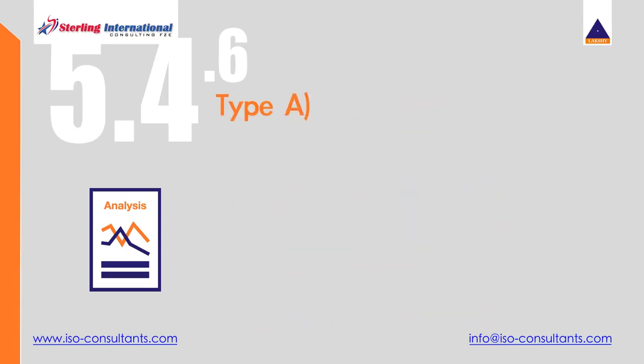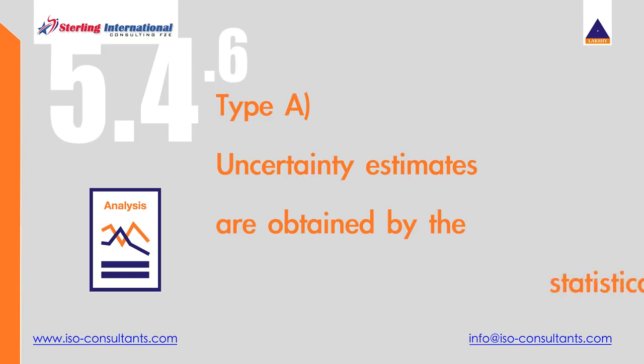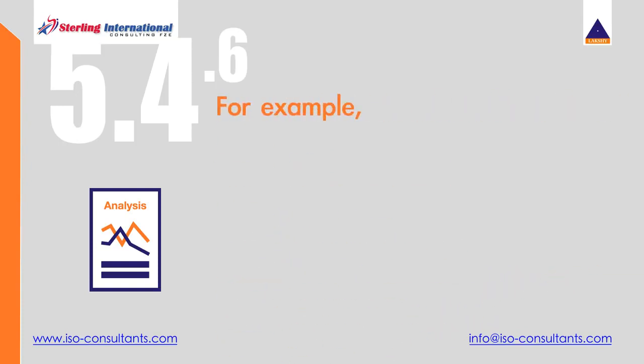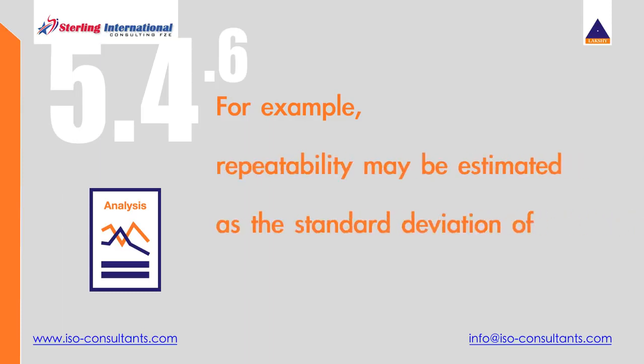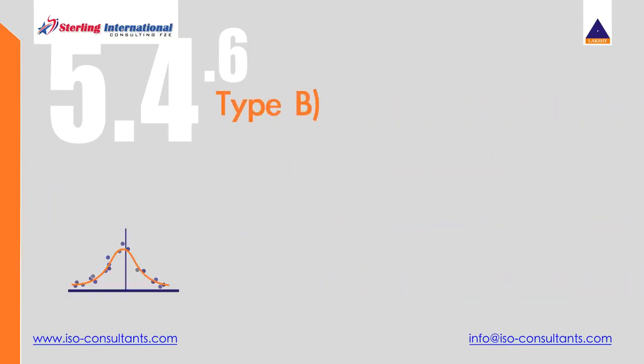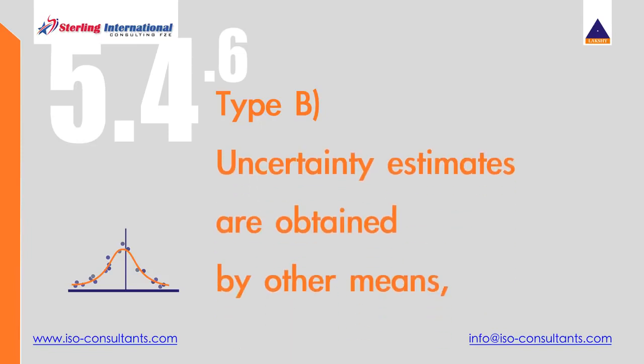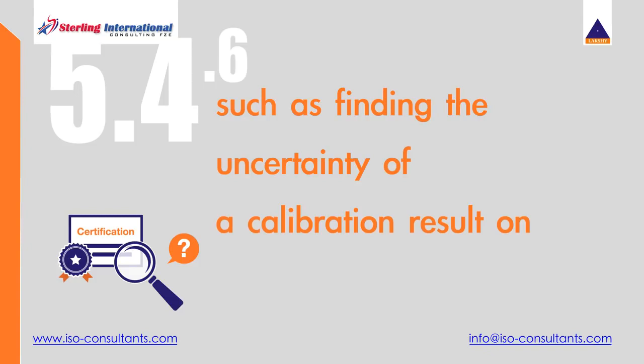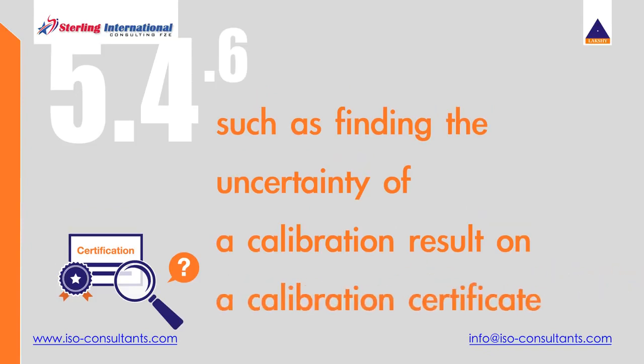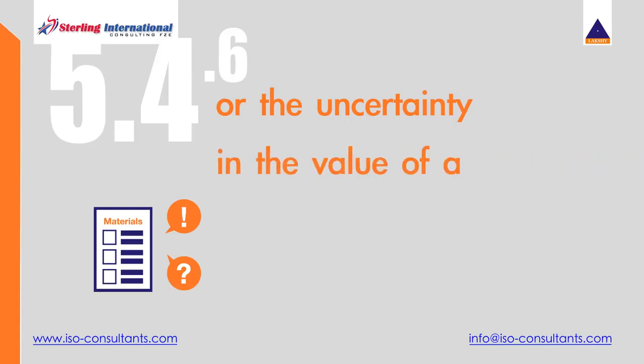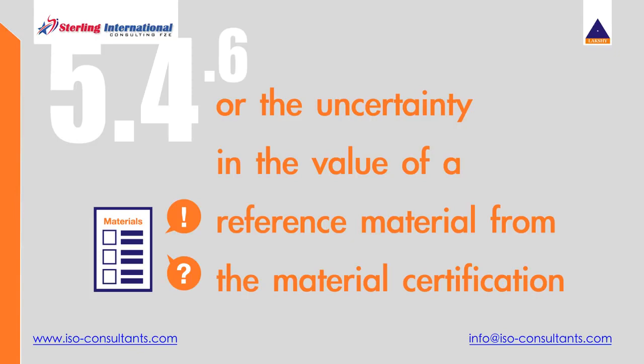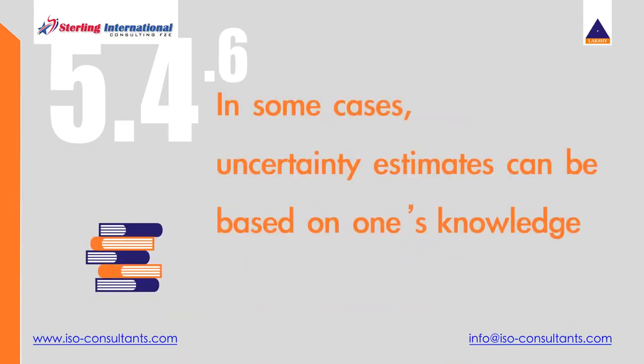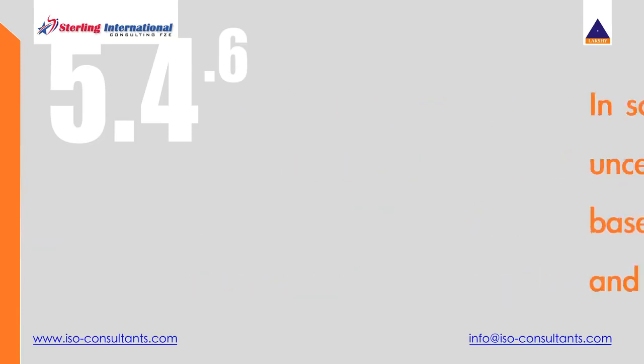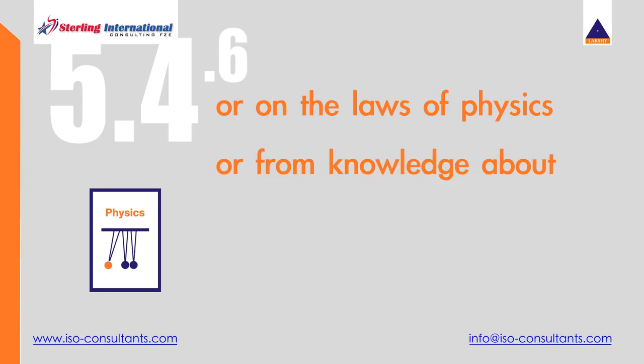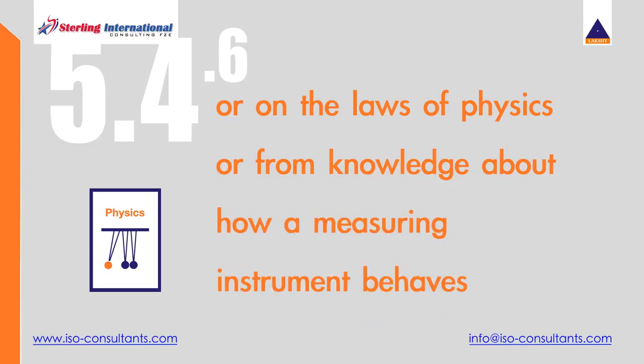1. Type A. Uncertainty estimates are obtained by the statistical analysis of data. For example, repeatability may be estimated as the standard deviation of a set of repeated measurements. 2. Type B. Uncertainty estimates are obtained by other means, such as finding the uncertainty of a calibration result on a calibration certificate, or the uncertainty in the value of a reference material from the material certification. In some cases, uncertainty estimates can be based on one's knowledge and experience, or on the laws of physics, or from knowledge about how a measuring instrument behaves.